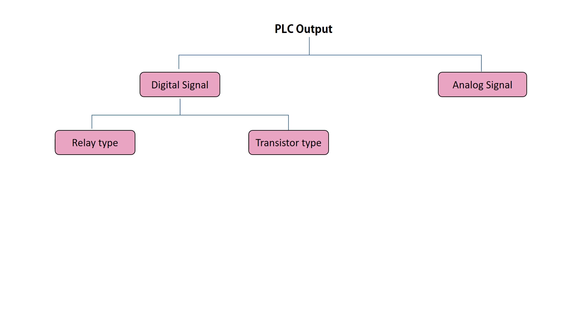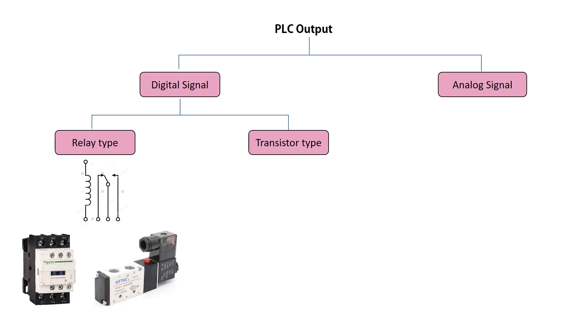PLC relay type outputs work similarly to normal relays, with the key difference being that the coil is energized by the PLC unit or program. Therefore, PLC relay type signals can switch both AC and DC loads, such as motor starters and pneumatic solenoid valves. These types of output devices receive digital signals.